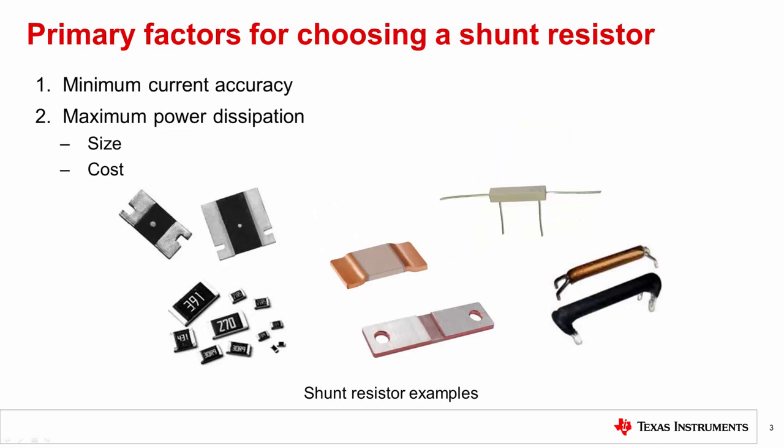Selecting the value of R_shunt is based primarily on two factors: the required accuracy at minimum load current and the power dissipation at maximum load current with its associated size and cost.